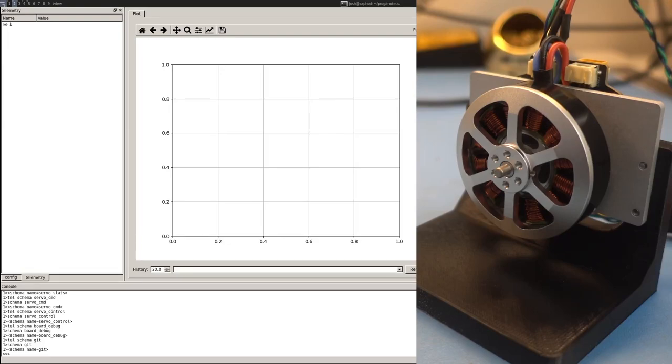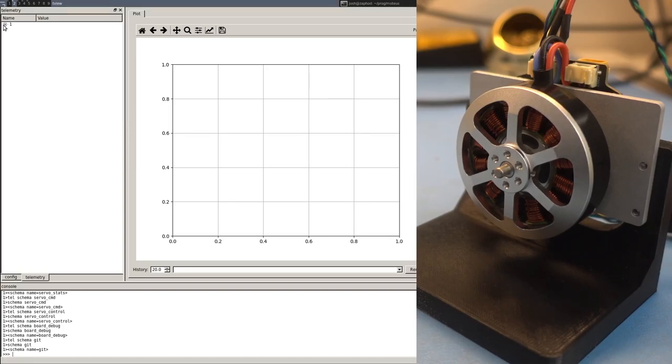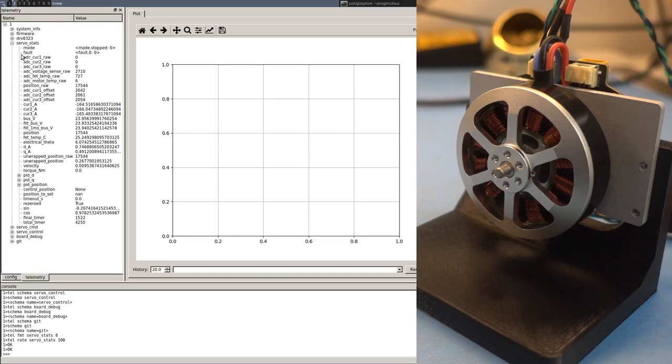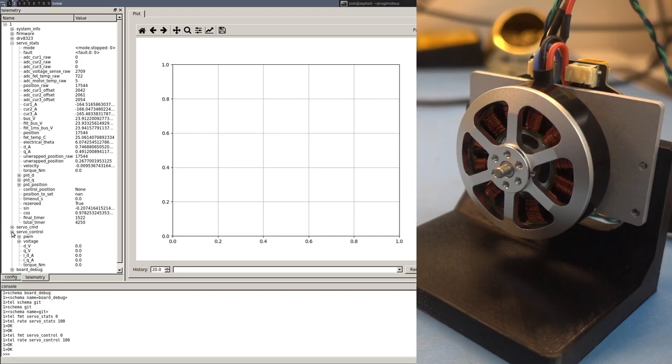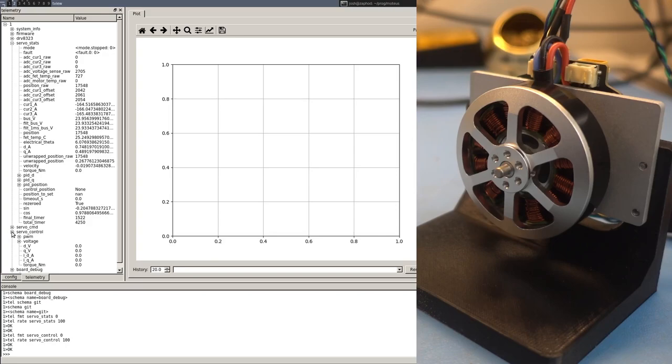This is a quick demo of a new control mode available in the Moteus controller that we're calling the stay within mode. In this control mode, there exists an upper and a lower bound within which the applied torque is zero. And if the position exits that upper and lower bound, then the normal PID controller is used to hold the position. And this can act as a set of virtual walls that apply to either side.